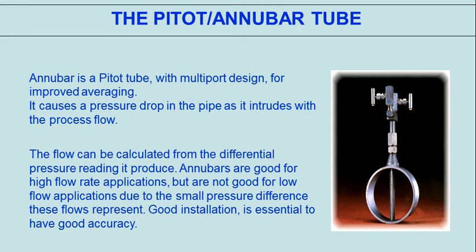The annubar is a pitot tube with a multi-port design that intrudes across the pipe as it measures the process flow. The flow can be calculated from the differential pressure reading. Annubars produce good results for high flow rate applications, but are not well suited for low flow applications due to the small differential pressure produced.